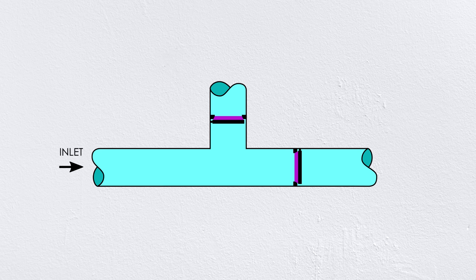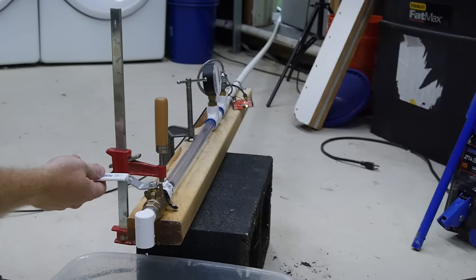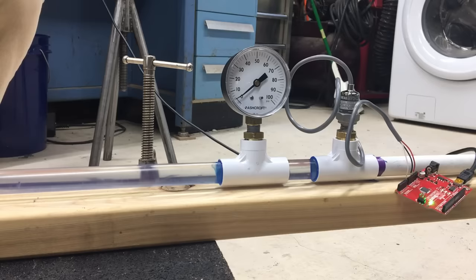Now the water is stopped in the pipe. It had kinetic energy, but now it doesn't. That means the kinetic energy was converted to something else. In this case, pressure. This is the definition of water hammer. Slamming a valve shut converts all the kinetic energy nearly instantly, creating a huge spike in pressure that can lead to stress and damage in pipe systems and connected equipment.